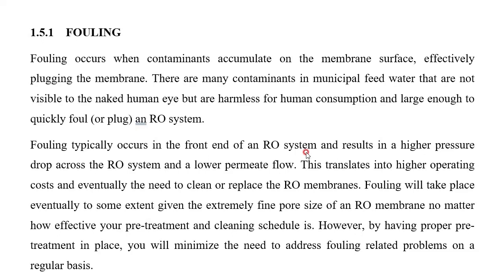It will block the pores of the membrane, so water will not be able to pass effectively through the membrane. It results in a high pressure drop across the RO system, and that results in a low permeate flow. That is, the amount of fresh or pure water we will be getting will reduce. So this will increase the operating costs, and we will eventually have the need to clean or replace the RO membranes.